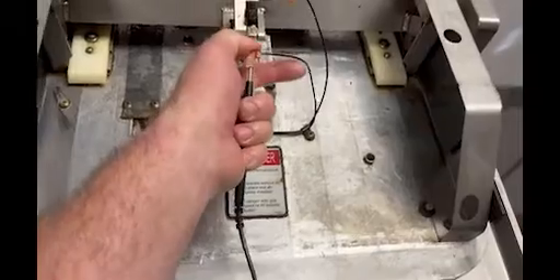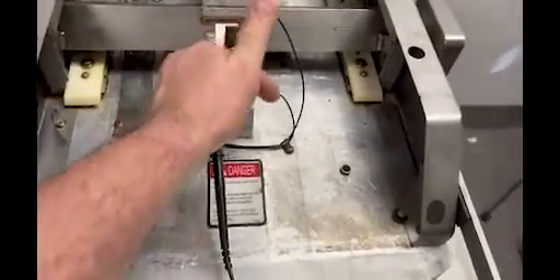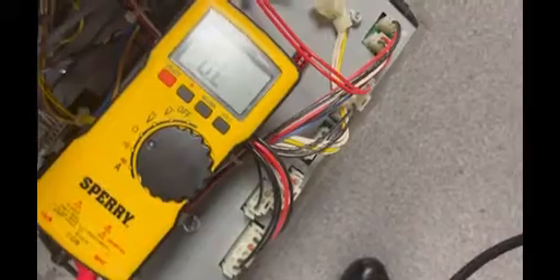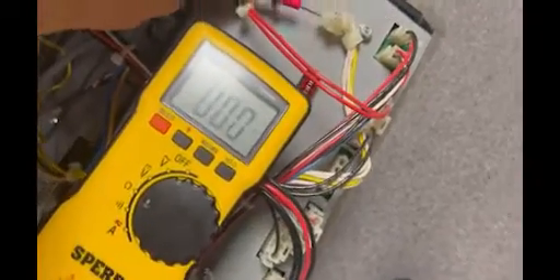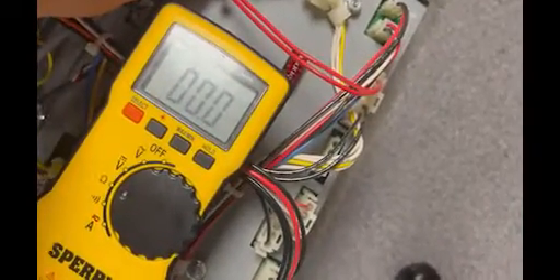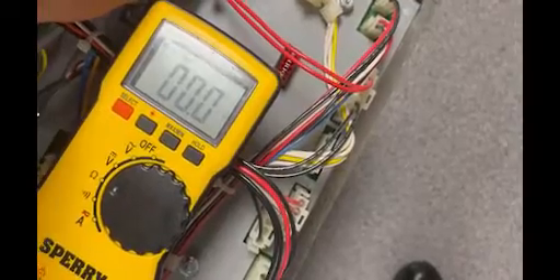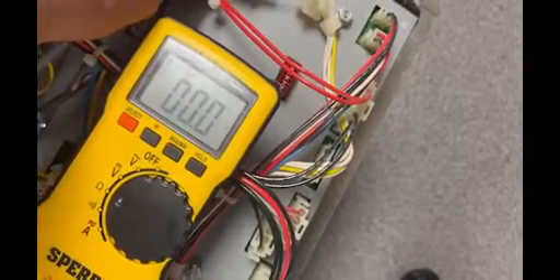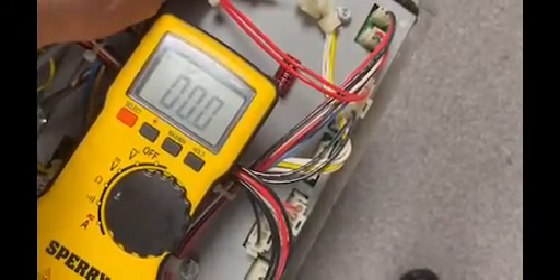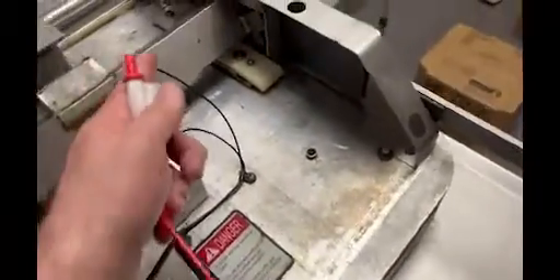I'm going to put one of the leads into one of these wires. If I followed the wire back, it comes up here, and when I test it, I should no longer have an open line, which I don't, showing me that whole line is good. If I still had an open line, I'd know there's an issue and a short somewhere. Then I can switch this one over into there.